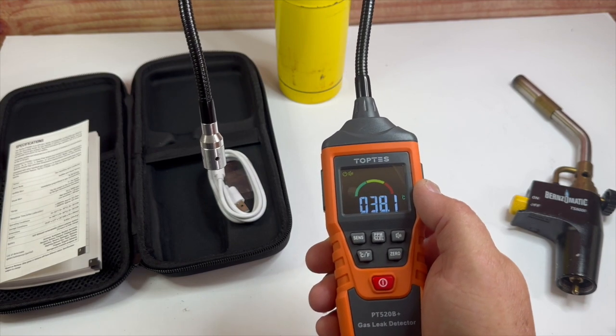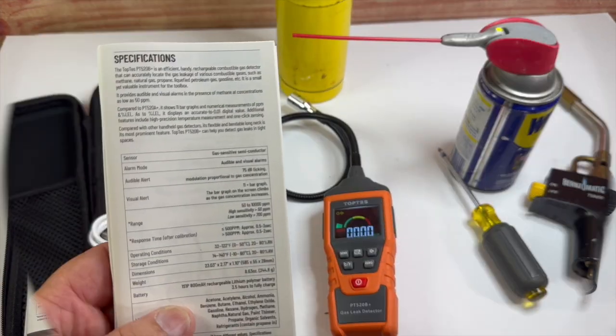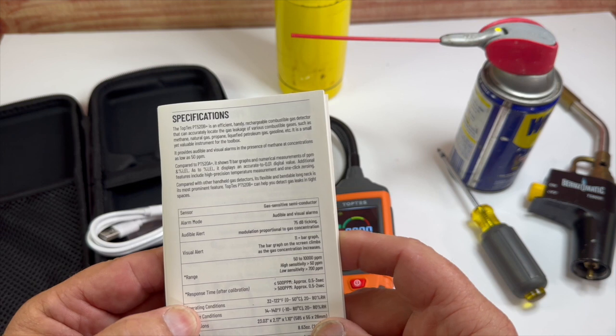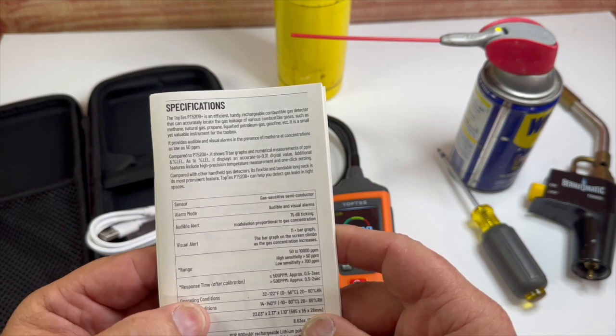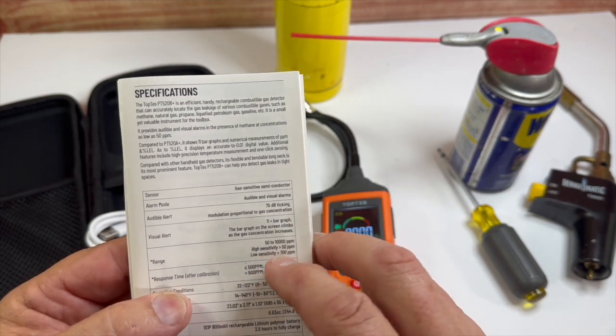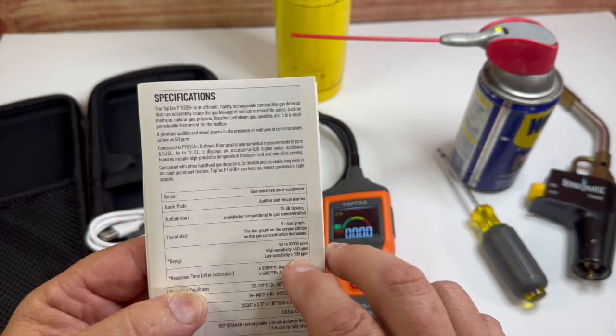This is the PTS208+ gas leak detector from Toptes — just a great tool. You can turn it around, bend it, and it comes with a great case. The specs: the sensor is a gas-sensitive semiconductor. Alarm mode is audible and visual. Audible alert is 75 dB ticking modulation, proportional to gas concentration. The visual alert is a 5-bar graph that climbs as gas concentration increases. The range is 50 to 10,000 parts per million. High sensitivity is 50 parts per million, and low sensitivity is 300 parts per million.